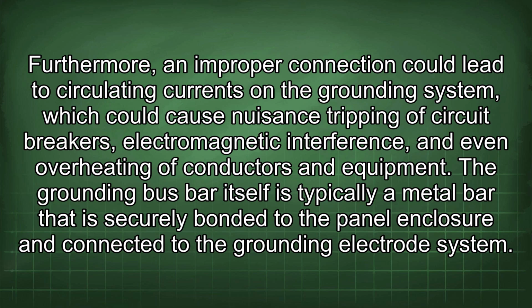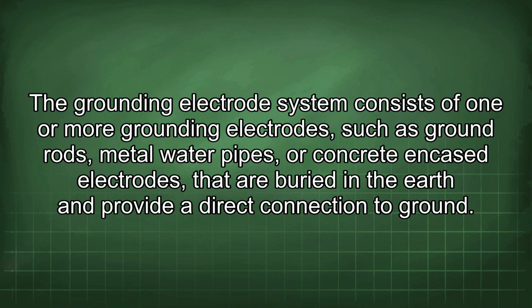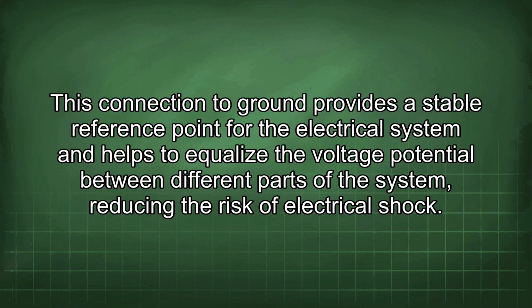The grounding bus bar itself is typically a metal bar that is securely bonded to the panel enclosure and connected to the grounding electrode system. The grounding electrode system consists of one or more grounding electrodes, such as ground rods, metal water pipes, or concrete-encased electrodes that are buried in the earth and provide a direct connection to ground. This connection to ground provides a stable reference point for the electrical system and helps to equalize the voltage potential between different parts of the system, reducing the risk of electrical shock.